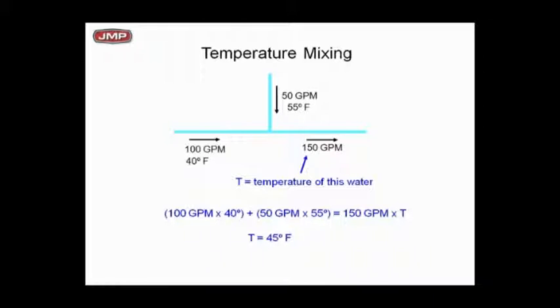This is probably the thing you need to spend a little time on because with chillers, you need to understand these blended temperatures and what happens. Real simple - if I got 100 GPM of 40 degree water mixing with 50 GPM of 55 degree water, I've got a total flow rate of 150 GPM leaving. So what will be the temperature? If you do the math here with a very basic formula, the temperature would become 45 degrees. You need to get comfortable making that calculation and being able to do it.